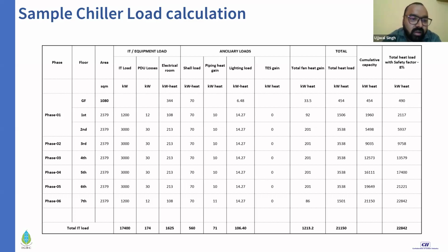Here they have distributed in 6 phases, each having an IT capacity of 3 megawatts. For these purposes, they calculated the losses incurred in the PDU, electrical room, building envelope, piping, and heat loads. There's no loss mentioned for thermal storage unit since they don't have one, but ideally if you have one, there will be some self-discharge loss too. Then total fan heat gain is the heat gain from your power system fans. By calculating all these factors, they were able to determine phase-wise how much heat load would be there in the data center.